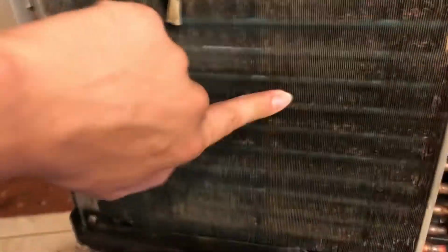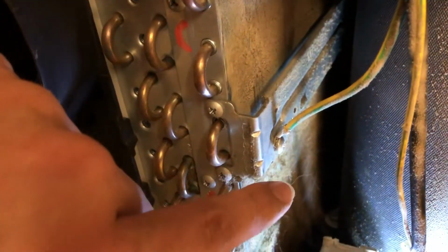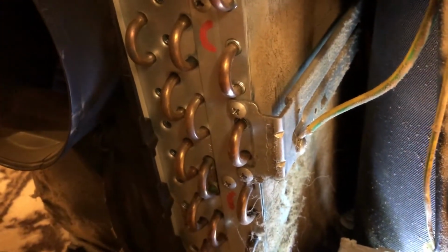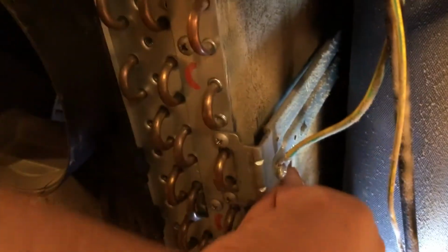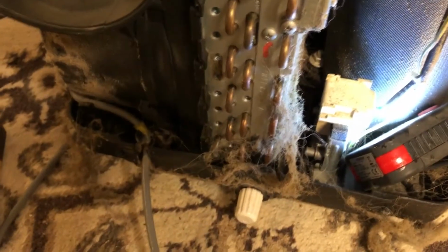This is the radiator, the lower radiator. The upper radiator is just for cooling the air, sucking it through. So here and out there. This is the cooler, this is, I guess, the vaporizer, I guess you call it. At least in this case, the low radiator, which cools the refrigerant again, and that stuff is hot. And what does it need to cool off? A lot of air, which will be sucked in through here and blown out through the hose. So, well, at least now we know the problem.